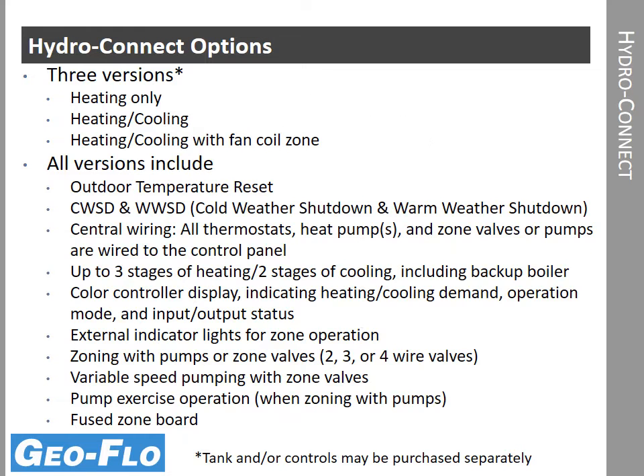Let's talk about HydroConnect options. There are 3 versions of controls: a heating-only control for typically radiant systems, a heating and cooling version, which allows both radiant zones and fan coil zones. And then there's a third option that is heating cooling with one fan coil zone.